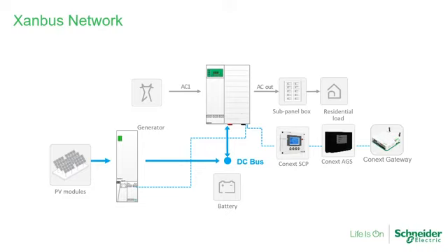Okay, so we talked a little bit about the network, the Xanbus network. I just wanted to give you a visual of what it would look like. So here we have the network where we have the MPPT80 daisy chain to the inverter, then the inverter's daisy chain to the accessories. In this case, we have a system control panel, automatic generator start, and at the end of the network, we have the gateway, which is our monitoring and control, and also allows you to connect to the cloud server inside too.